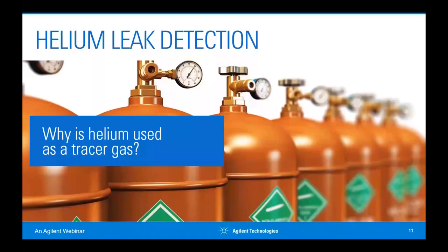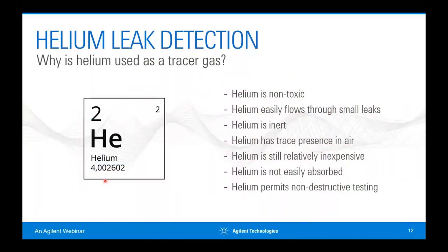So why helium? Helium is a very interesting gas with excellent properties for leak detection. It's totally inert — it won't affect your process or product in any way. It's non-toxic and a very small molecule, so it can easily flow through the types of leaks we're looking for. It's relatively inexpensive and easy to get through industrial gas suppliers. It's at a very low concentration in air — about five parts per million — making it easy to differentiate from background. It allows non-destructive testing.